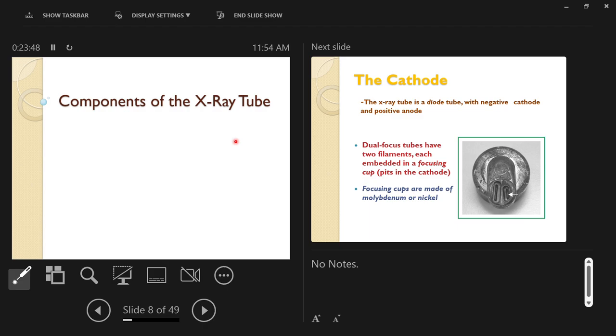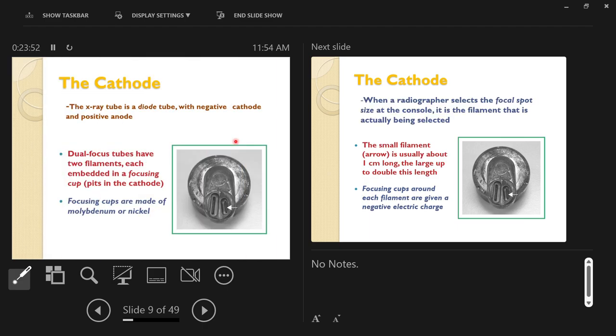Let's look at what an x-ray tube is made out of, starting with the source of electrons. The side of the x-ray tube that has the source of electrons is called the cathode. The cathode is on the negative side of the x-ray tube. X-ray tubes can be called a diode tube because they only allow electricity to travel in one direction, from negative to positive.